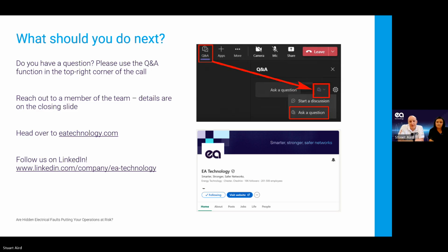So can you estimate the end of life of a remaining asset, and can it be reversed in any way, or to plan replacement? And is it truly non-intrusive, or would they need to power down? All the measurement techniques that we've used here, TEV and ultrasonic, are completely non-intrusive, really. HFCTs are a bit of both. It depends if you can physically install those under normal operating conditions, so you might need to power down for that. But yes, transient earth voltage and ultrasonic is generally completely non-intrusive.